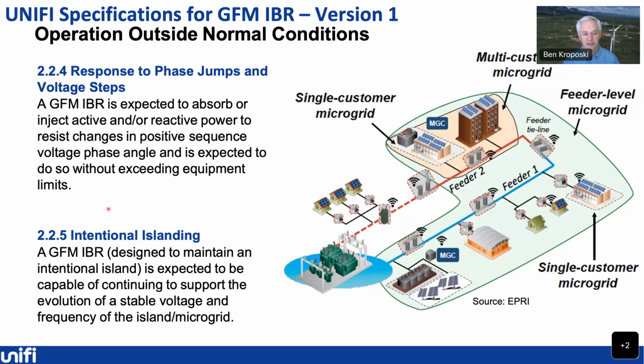And then finally, intentional islanding. When we go to a microgrid type mode and we disconnect from the rest of the grid, they need to be able to maintain stable voltage and frequency inside that island system. So you may have a small customer-sided microgrid or a much larger microgrid, depending on your setup. If you have enough grid-forming inverter technologies in there, we want them to make sure they maintain stable operations in those microgrids.